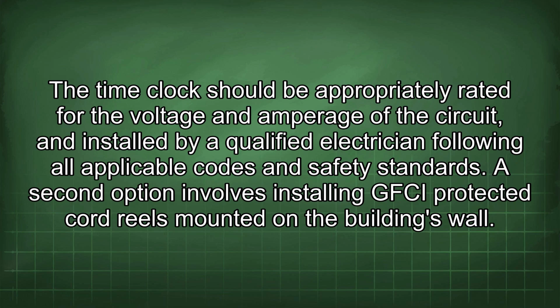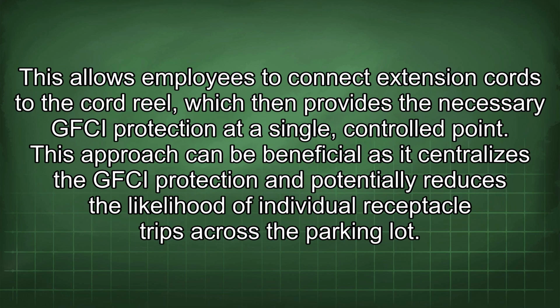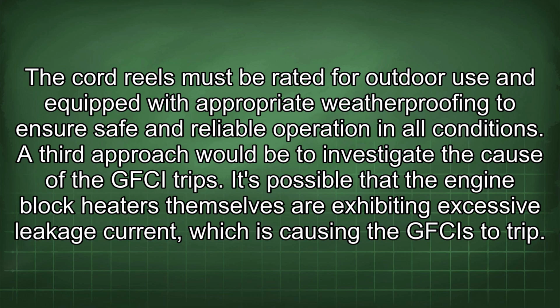A second option involves installing GFCI protected cord reels mounted on the building's wall. This allows employees to connect extension cords to the cord reel, which then provides the necessary GFCI protection at a single control point. This approach can be beneficial as it centralizes the GFCI protection and potentially reduces the likelihood of individual receptacle trips across the parking lot.